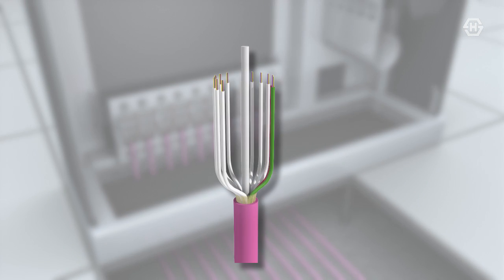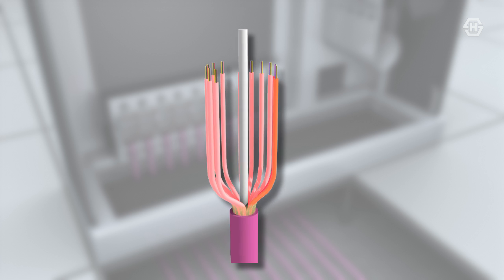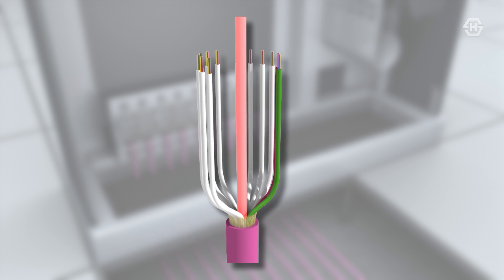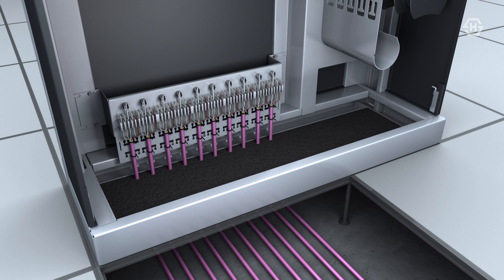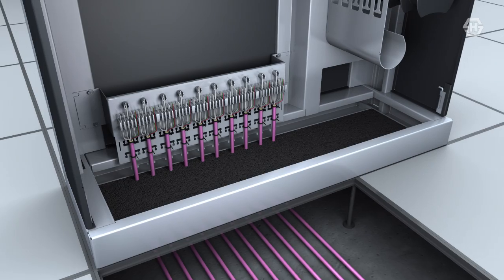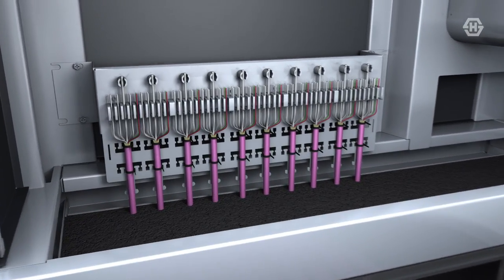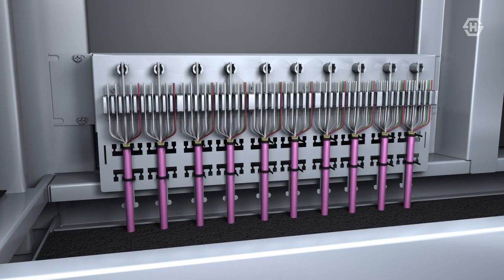Loose tube cables from 12 up to 144 fibres require the highest level of protection within the Lisa NGR. For this reason, we deploy a three-tier fixing method whereby the cable jacket, loose tube and central strength member are securely fixed to the rack. This provides optimum strain relief and bend radius protection for the most important links in the data center. If we look first at the full width breakout plate, we can see how multiple cable types and fiber counts can be securely anchored to the entry point of the rack.